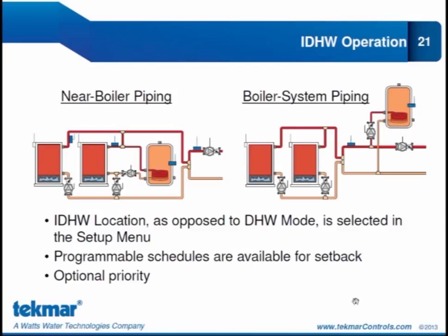The 284 does have setback capability, so you can operate the indirect domestic hot water on schedules. And just like the other controls, this has optional priority for the indirect domestic hot water operation. One thing I do want to point out, I know I said it before, but the near boiler piping must be on boiler number 4. So in this system we only have 2 boilers. We would probably configure this one to be boiler number 1, turn boilers 2 and 3 off, and set up boiler 4 in this case, so that we have that near boiler piping for the indirect domestic hot water operation.